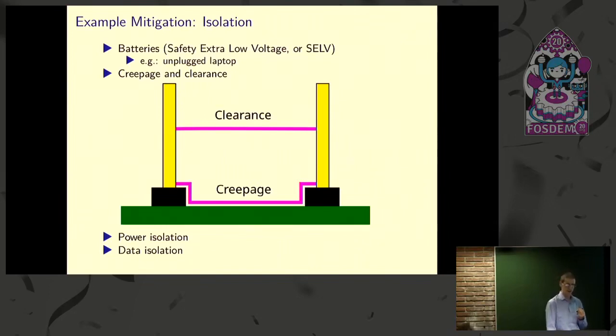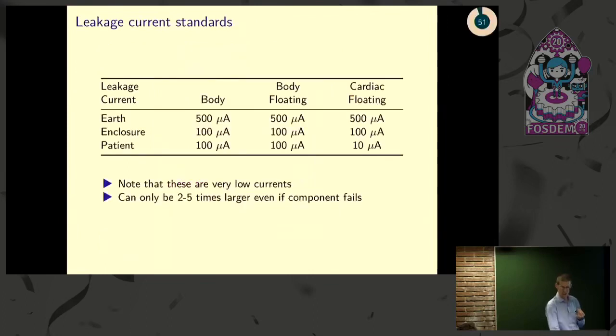If you do that, you want to make sure there are gaps, which we call clearance, between the isolated parts, both across the surface of the board and off the surfaces, because surfaces can get moist or dirty, so that distance is usually larger. There are a lot of standards, but 8 millimeters is usually a pretty good rule of thumb, and it's on the safer side. We'll skim over this because we're running out of time, but the important thing is there are standards for how much current your device can run through a person.